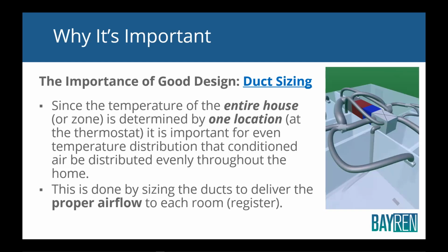Okay. Now, the other important part of a good design is duct sizing. If you think about it, you're trying to make the temperature in a house even throughout the entire house, and you're doing that by monitoring the temperature at essentially just one location, which is the thermostat. So in order for the entire house to be at the same temperature while you're monitoring it at one spot, you need to do a good duct design. What that does is it makes sure that each room gets the right amount of airflow proportional to that room's load. And what that means is you have to do a room by room load calculation. So previously we were talking about equipment sizing, and what you typically do for that is something called a block load.